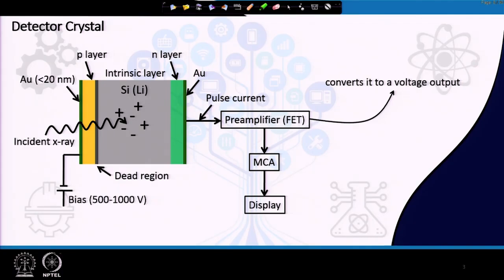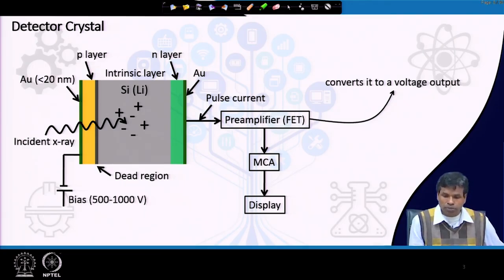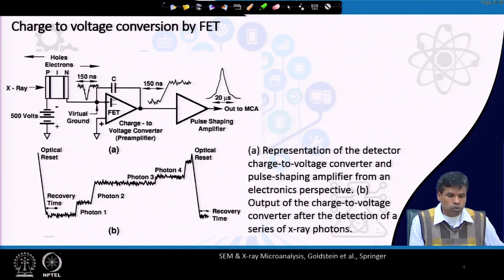This detector is placed at a lower temperature of 77 Kelvin so that its conductivity will be less. In addition, this PIN junction is reverse biased so that we can separate out the electron-hole pairs generated due to the incident X-ray and collect the current generated in the detector. That current is amplified with a field effect transistor and then converted to a voltage output. The FET converts the charge or current from the X-ray detector to voltage, which is then deposited to a capacitor.